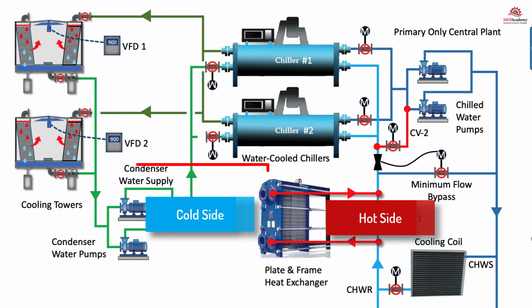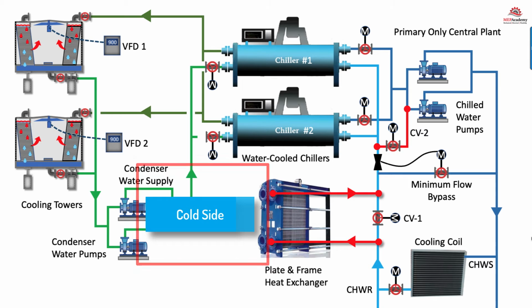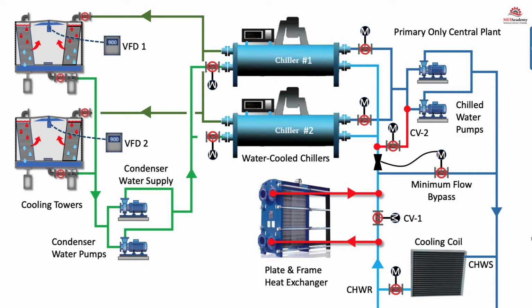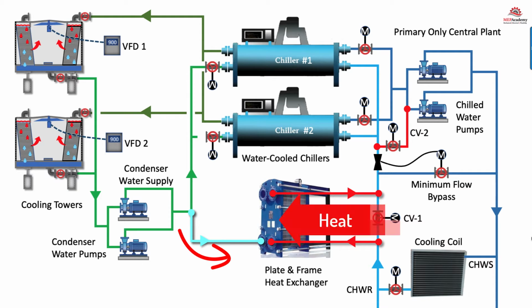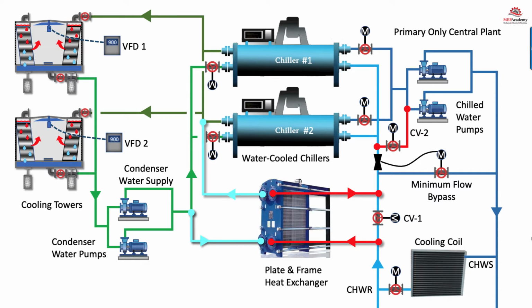For the cold side of the heat exchanger, we need to connect the condenser water piping in parallel with the chillers and pipe the cold water coming from the cooling tower basins so that it flows into our heat exchanger where it will absorb the heat through the plates from the chilled water return. The heat will then be carried by the condenser water to the top of the cooling tower where it will reject the heat to the atmosphere. We need to install a control valve, CV-1, to prevent the flow from entering the heat exchanger when it's not in economizer mode to avoid additional pressure drop on the pumps.